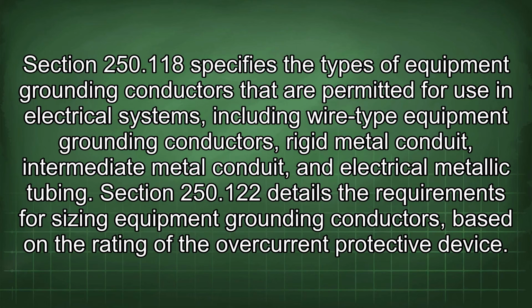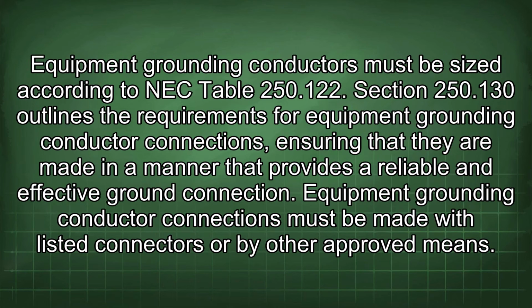Section 250.118 specifies the types of equipment grounding conductors that are permitted for use in electrical systems, including wire-type equipment grounding conductors, rigid metal conduit, intermediate metal conduit, and electrical metallic tubing. Section 250.122 details the requirements for sizing equipment grounding conductors, based on the rating of the overcurrent protective device. Equipment grounding conductors must be sized according to NEC Table 250.122.